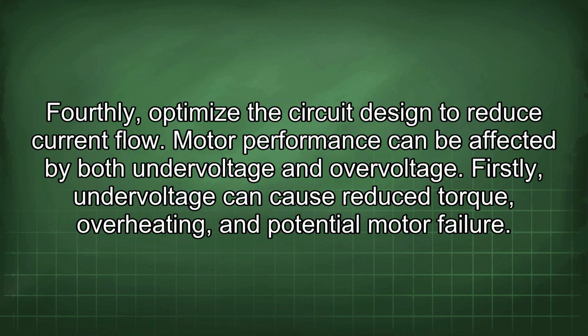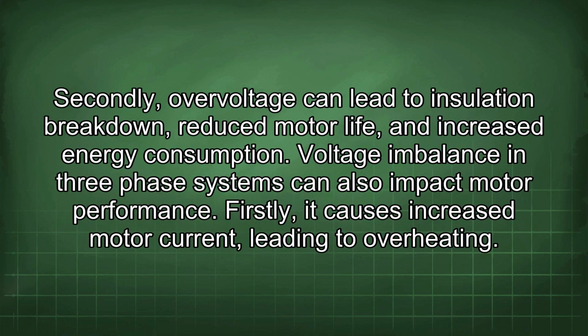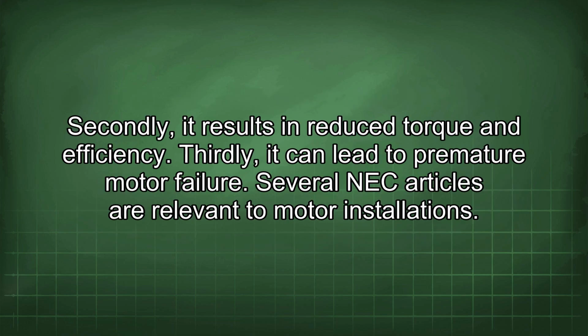Motor performance can be affected by both undervoltage and overvoltage. Firstly, undervoltage can cause reduced torque, overheating, and potential motor failure. Secondly, overvoltage can lead to insulation breakdown, reduced motor life, and increased energy consumption. Voltage imbalance in three-phase systems can also impact motor performance. Firstly, it causes increased motor current, leading to overheating. Secondly, it results in reduced torque and efficiency. Thirdly, it can lead to premature motor failure.